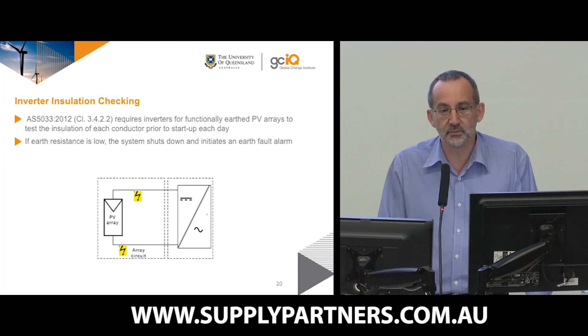Another thing that's probably worth noting is that the arrays out there are all negatively earthed. And unlike the unearthed systems that you're familiar with, your transformerless inverters, these larger systems have different configurations. One of the things we particularly insisted upon in our installation was that our inverter be provided with the capability to check the insulation each morning. That's an AS5033 requirement, which, particularly now that the new 5033 only applies up to 240 kilowatts, larger arrays will not have to have, but we insisted upon it.